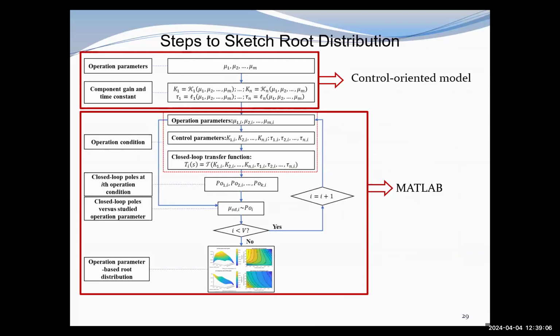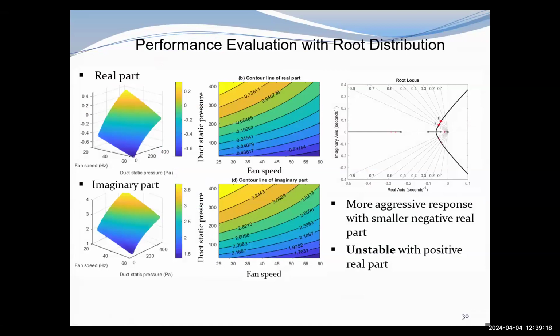So here we developed the steps to sketch these root distributions with the developed control-oriented models. For the traditional root locus, we only have one variable, that is the controller gain. But for the root distribution, we will have multiple variable parameters, because normally we will have more than one variable operation parameter, and the figure will become more than 2-dimensional, 3-dimensional, or 4-dimensional. For example, for this fan speed control system, we have 2 variable operation parameters. One is the fan speed, one is the duct static pressure. And correspondingly, the root distribution figure will be a 4-dimensional figure.